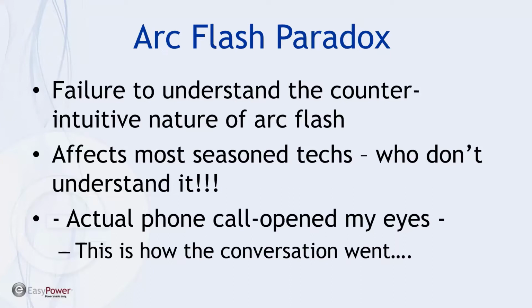He said, first of all, we want to start a new project. And I'm going to pick up an icon from the equipment palette for the utility icon. And he said, the first thing we have is a utility transformer. So we pick up the 2-winding transformer, touch the pigtails, click again. The tool knows that we need a voltage assigned to this intersection. He said his incoming voltage was 12.8 kV.